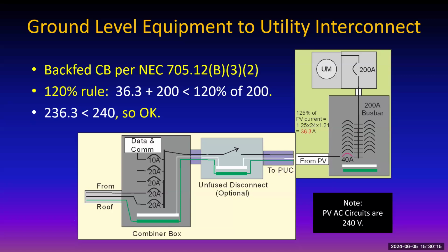Okay, and all the circuits coming down from the PV inverters are 240 volts AC. There are 208 volt AC outputs available in microinverters. If you happen to have a 208-volt system, they're a special order, a different model.